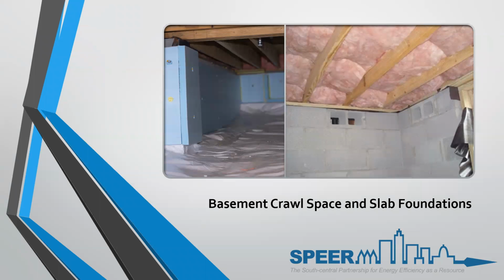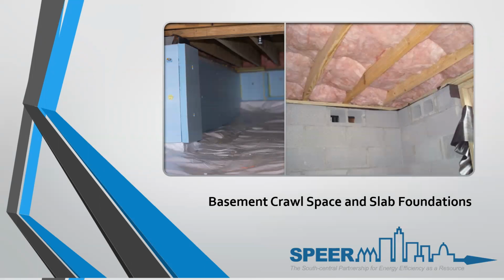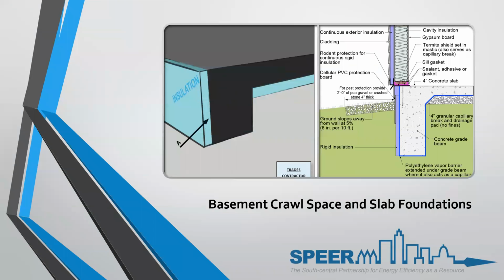Some people call those tiger teeth, and it's holding that insulation in place. It is kind of compressing at those areas, but the intent is you need to hold that insulation in contact with the conditioned floor above. And so that is meeting the intent.